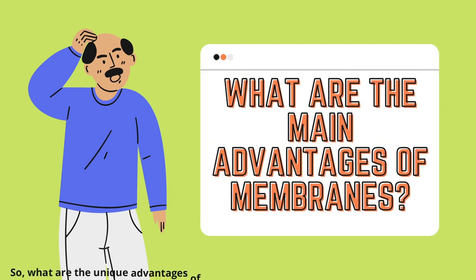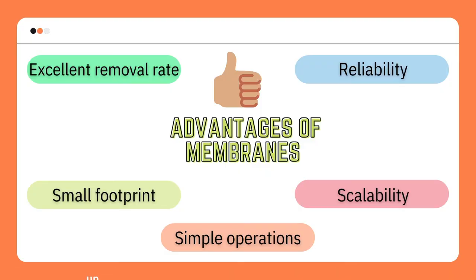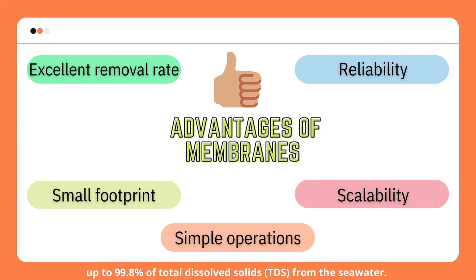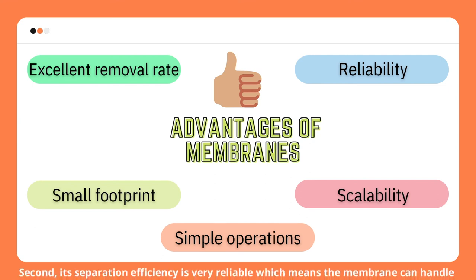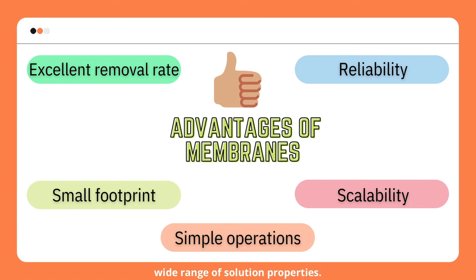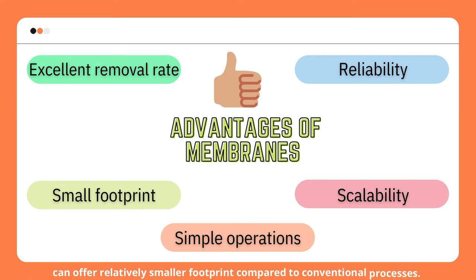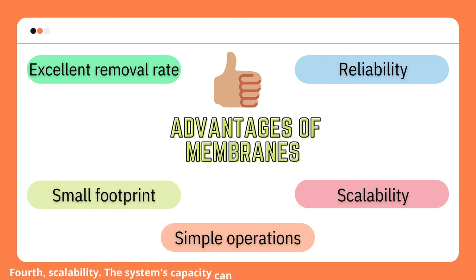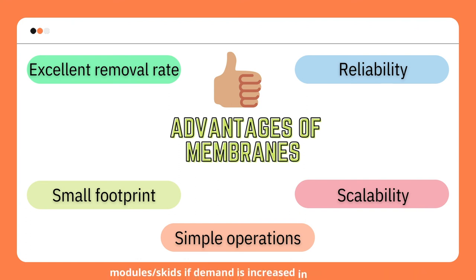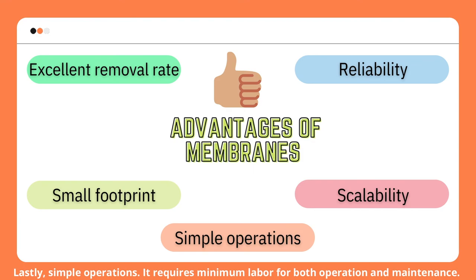What are the unique advantages of membranes compared to conventional filtration methods? First is excellent removal rate — for instance, reverse osmosis membrane can remove up to 99.8% of total dissolved solids from seawater. Second, its separation efficiency is very reliable, meaning the membrane can handle a wide range of solutions. Third is small footprint: due to its compact module design, the membrane system offers a relatively smaller footprint compared to conventional processes. Fourth is scalability — the system's capacity can be easily upscaled by adding more membrane modules if demand increases. Lastly, simple operations, as it requires minimum labor for both operation and maintenance.